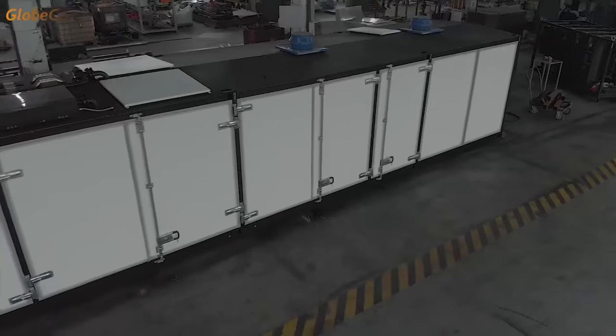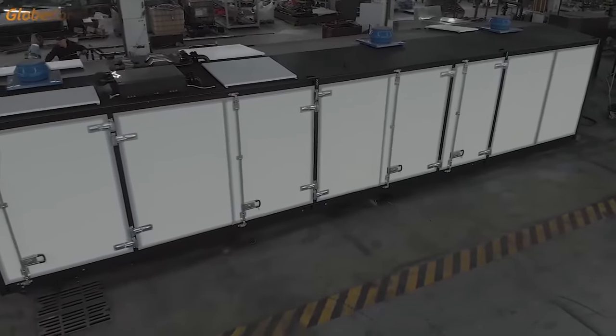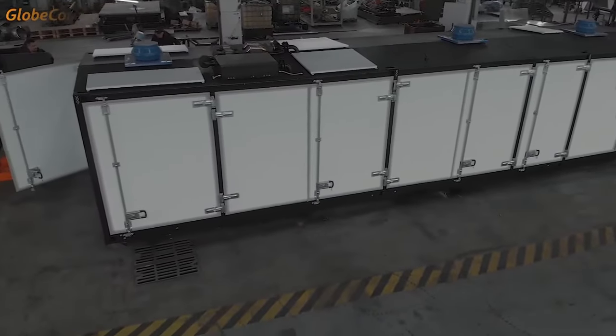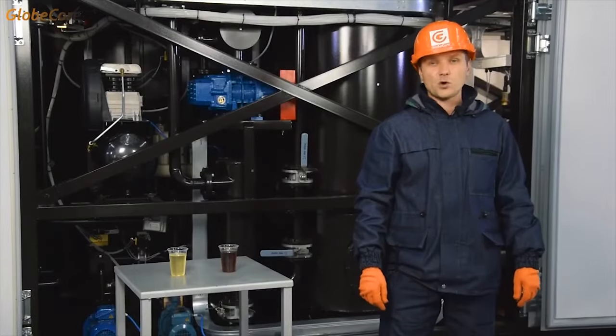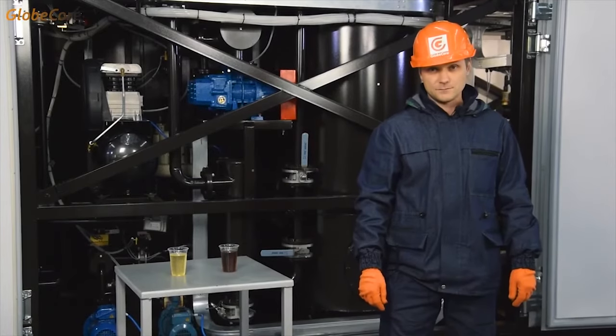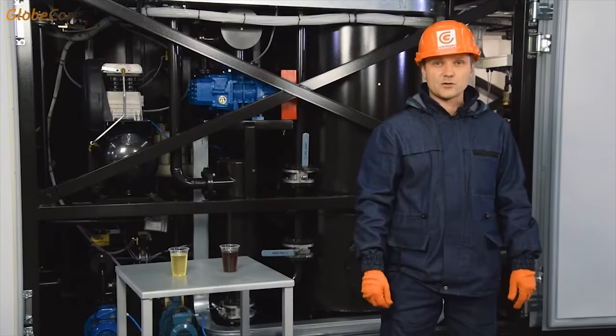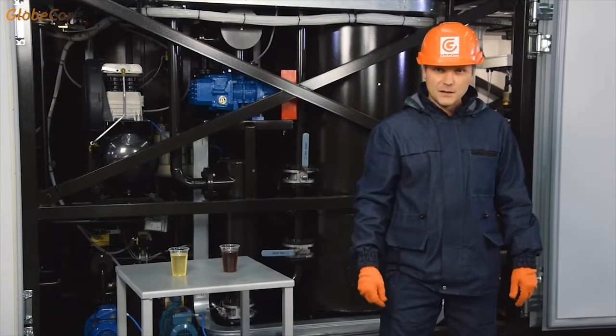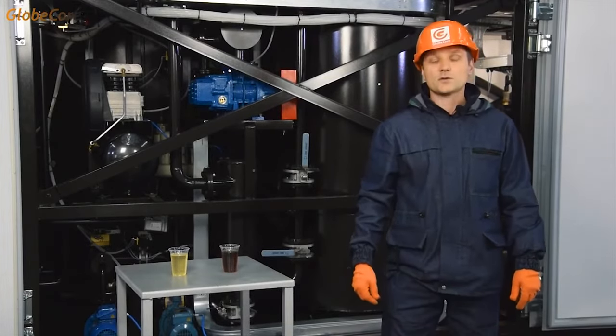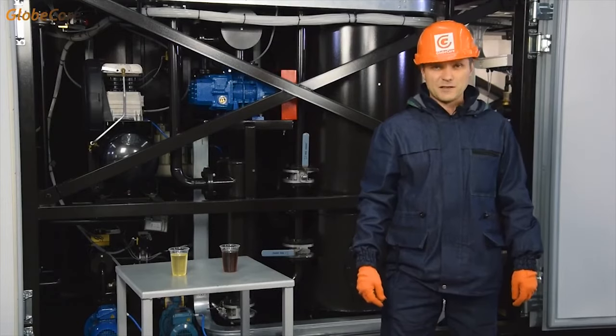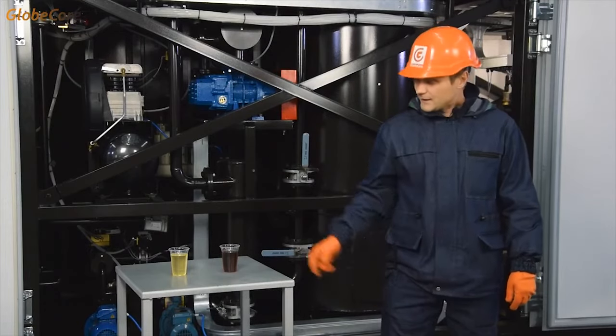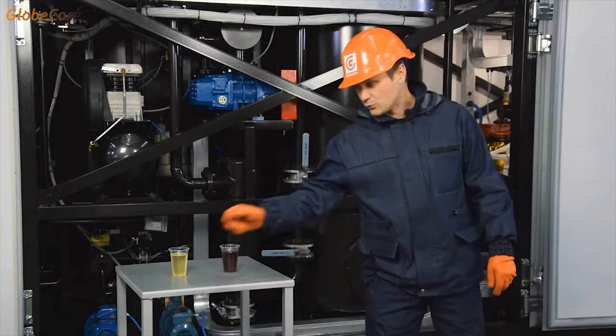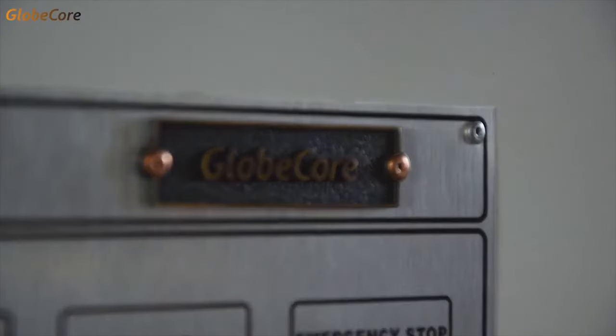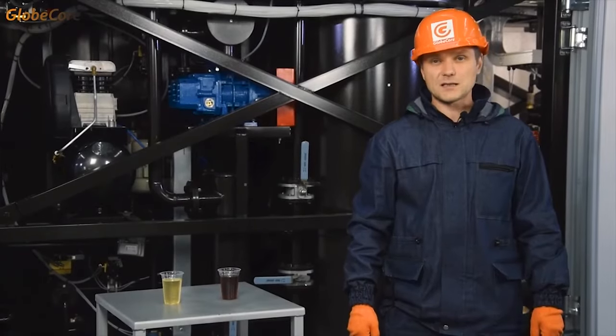This means that the CMM-6R can restore old unusable transformer oil to the quality and performance of new oil, no less. This alone is impressive. The fact is that the machine takes used oil, basically a waste material, and a problematic one at that, which requires elaborate disposal procedures, and makes an actually usable and marketable product out of it. Let me say this again, a usable product is made from waste. To say nothing of the fact that the global deposits of crude oil used for the production of transformer oil are not getting any larger. This alone is enough to respect this machine.